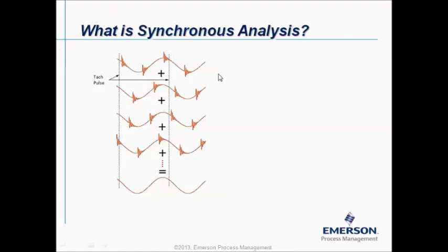Now, because the waveform is always starting when the tach pulse is coming in and the position of the shaft is always the same, all the vibration data related with the shaft speed, and that is called synchronous data, will be represented in the same way and at the same moment. However, all data that is coming from other shafts or from bearing problems for example, they will always happen at different moments in time. Now, if we average this, the synchronous data at the end is still very dominant, but all the non-synchronous data is out of the stored waveform, is averaged out.